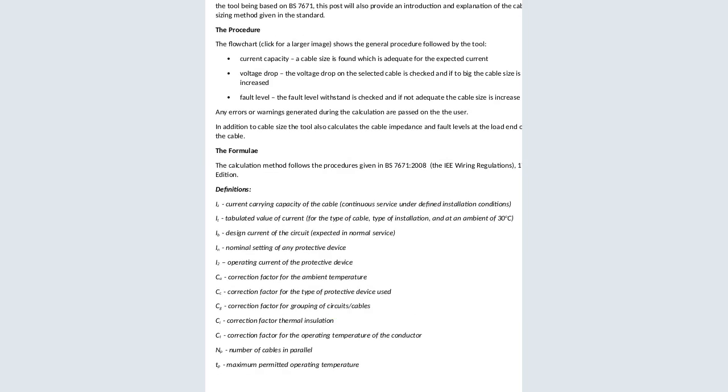Any errors or warnings generated during the calculations are posted to the user. So, in addition to cable size, the tool also calculates the cable impedance, fault levels and the load at the load end of the cable. So the formula calculation method follows the procedure given in this standard. So we have some of the definitions that we are going to use in this calculation.